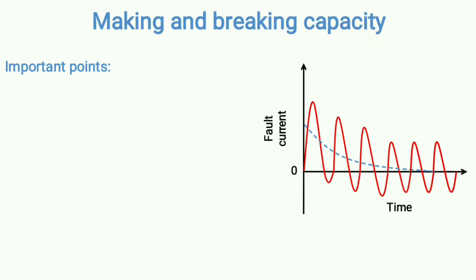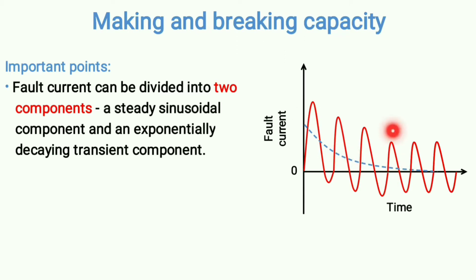Whenever a fault happens, the fault current can be divided into two components: a steady sinusoidal component and an exponentially decaying transient component. As you can see in this figure, the blue dotted line represents the exponentially decaying transient component. Due to the presence of this decaying component, the fault current becomes asymmetrical in nature. But as time goes on, this component gets reduced and after some time the fault current again becomes symmetrical.